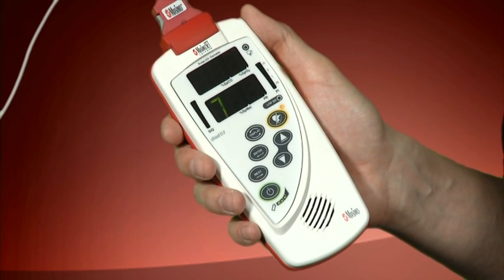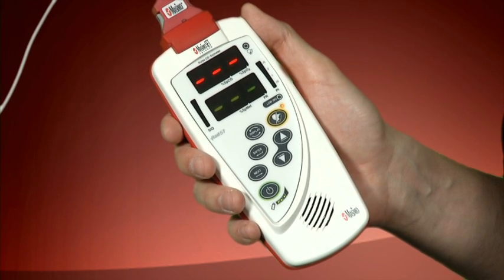While the device is detecting the pulse, scrolling zeros followed by dashed lines will appear on the screen. This can take anywhere from 20 seconds for the SpO2 and pulse rate to 120 seconds for SpCO. It is important to note that the dashed lines do not mean that the value is 0.